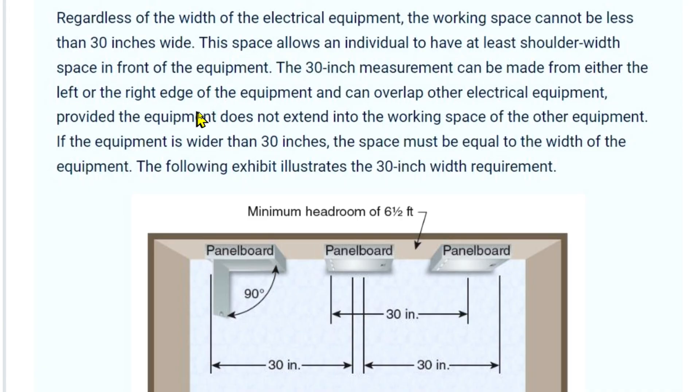And can overlap other electrical equipment provided the equipment does not extend into the working space of the other equipment. If the equipment is wider than 30 inches, the space must be equal to the width of the equipment. The following exhibit illustrates the 30 inch width requirement.